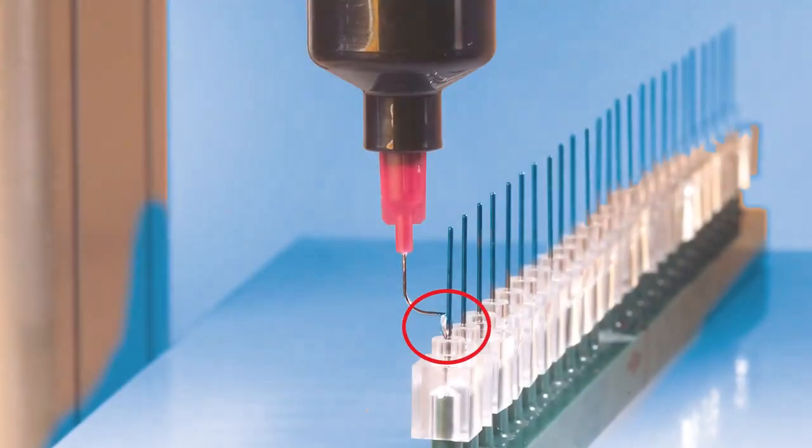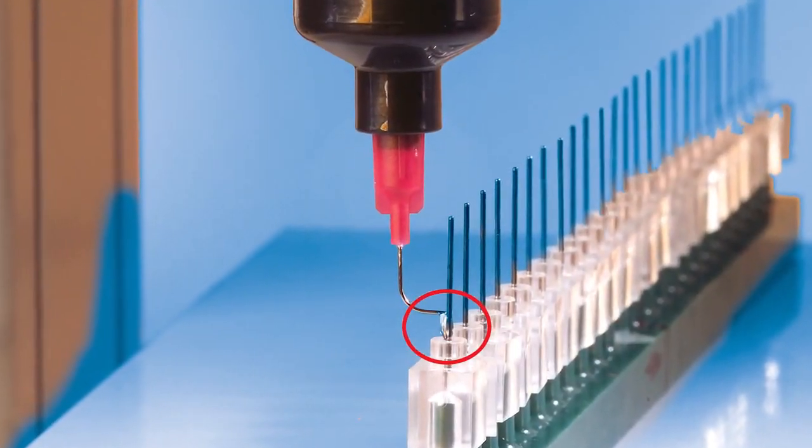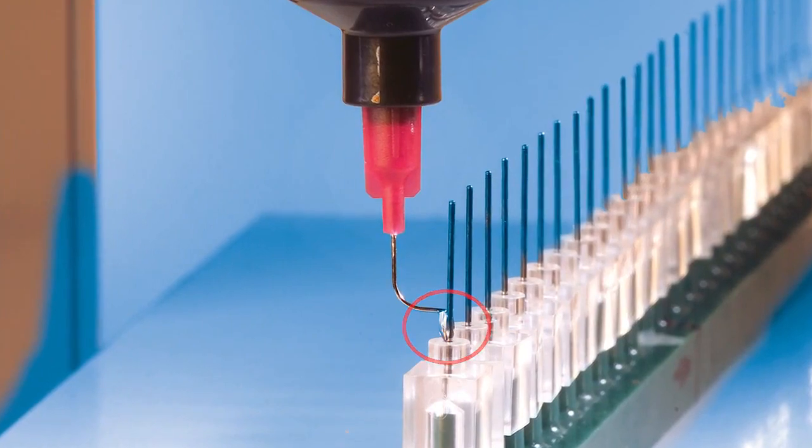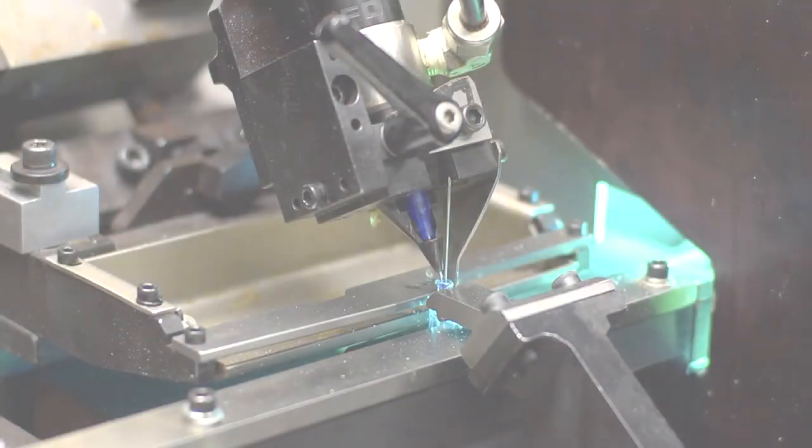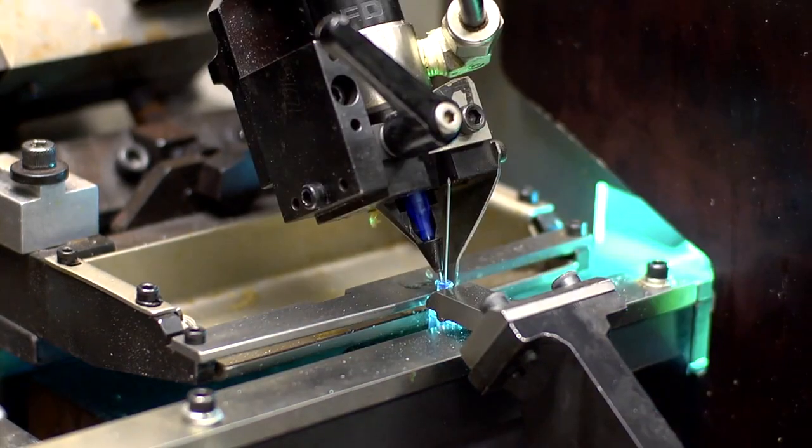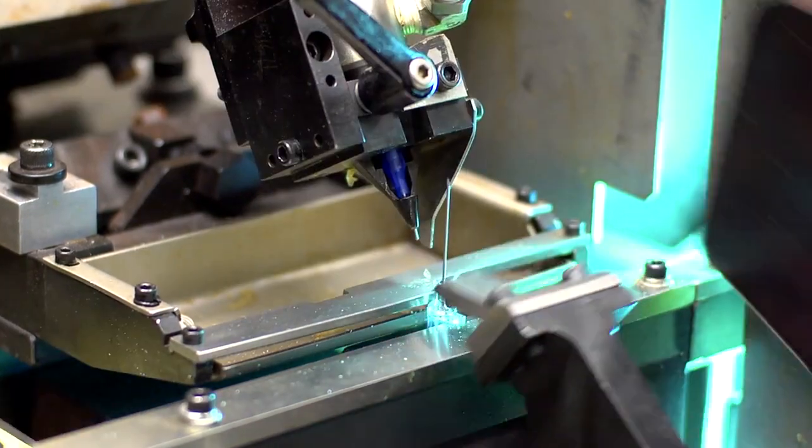It is critical that this joint is well sealed to prevent fluid such as blood or medicine from leaking. Henkel's light cure adhesives provide the highest needle assembly throughput due to their rapid cure.